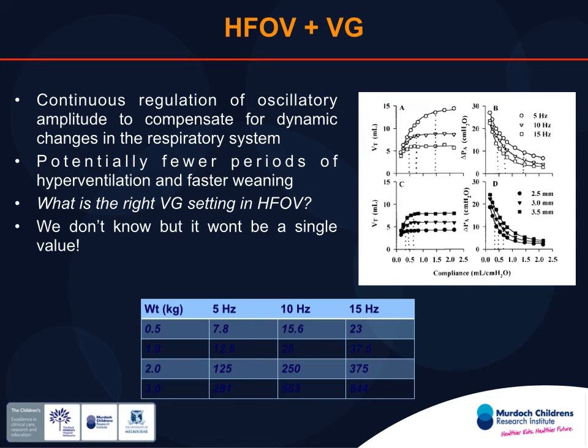Because you could set 2 mil per kilo and have a baby at 15 hertz working beautifully, and then you could change your frequency, and if you don't change your volume guarantee setting, you will get a change in DCO2 that may be good or may be bad, depending on how you change your frequency. Okay, because by virtue of changing frequency, you change your tidal volume. The volume guarantee will still be trying to do the same thing, 2 mil per kilo. But it will have an influence on your DCO2.